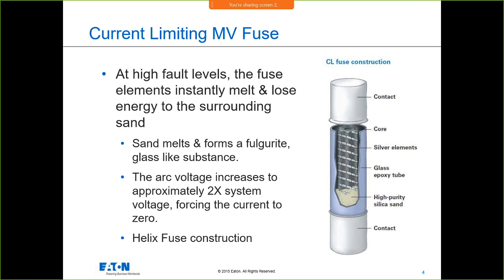And if you look, remember I talked about the elements inside. It's hard to tell in here, but in this example, this element is actually coiled something like this. It's doing this basically all the way around because I need so many of those elements in there. You have sand in those just like you have in the low voltage power fuses. And again, you have that helix fuse construction because I need a lot of those pinch points. Silver elements, glass epoxy tube, all that good stuff.